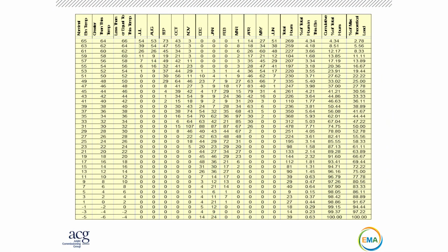And now we're going to look at this little chart here in terms of the cycle efficiency part of it. I know this is kind of busy, so I'll zoom in on it in a second. But this is ASHRAE data for Chicago. I'm from Chicago, so that's what we have. But it looks at the heating degree day hours throughout the year, and it shows the outside air temp, and then how many hours of each month your operating hours within that outside air range, right? So if we zoom in a little bit, this is kind of towards the bottom of the scale. And our design day, which in Chicago is about a -5 outside air temp. We do get a little bit colder, but -5, -10, somewhere around there.